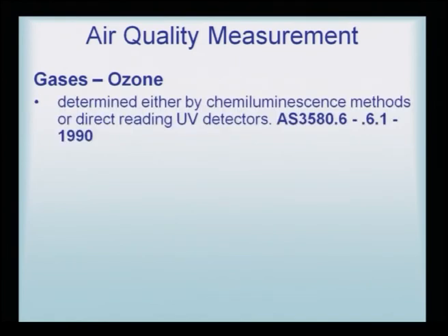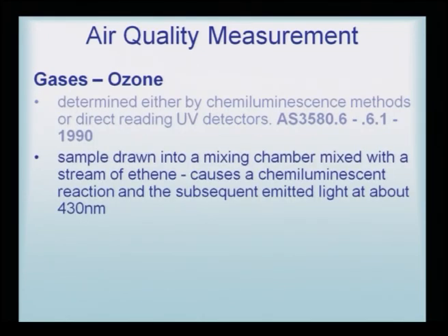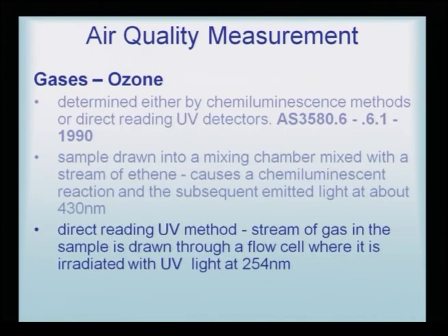Ozone is determined either by the chemiluminescence method or by direct reading by UV detector. The sample is drawn into a mixing chamber and mixed with a stream of ethylene, which causes a chemiluminescent reaction, and the subsequent emitted light is at about 430 nanometers. In the direct reading UV method, a stream of gas in the sample is drawn through a flow cell where it is irradiated with UV light at 254 nanometers. So, it is a very simple UV method of analysis, and it is a foolproof method of analyzing ozone.